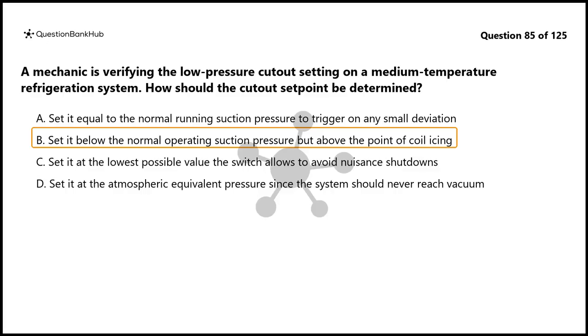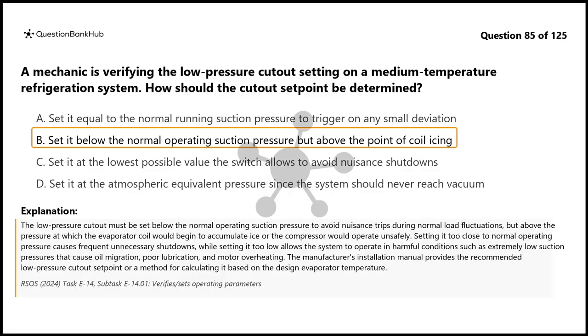The correct answer is B. The low-pressure cutout must be set below the normal operating suction pressure to avoid nuisance trips during normal load fluctuations, but above the pressure at which the evaporator coil would begin to accumulate ice or the compressor would operate unsafely. Setting it too close to normal operating pressure causes frequent unnecessary shutdowns, while setting it too low allows the system to operate in harmful conditions such as extremely low suction pressures that cause oil migration, poor lubrication, and motor overheating. The manufacturer's installation manual provides the recommended low-pressure cutout setpoint or a method for calculating it based on the design evaporator temperature.